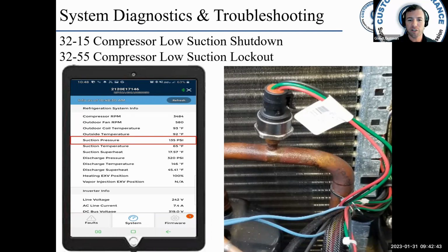Okay, 3215 and 3255. It's compressor low suction shutdown and compressor low suction lockout. All right. It's looking at the transducer. Okay, the transducer takes the place of the pressure switch. So there is no pressure switch. It's just the transducer reporting, hey, we got low suction.